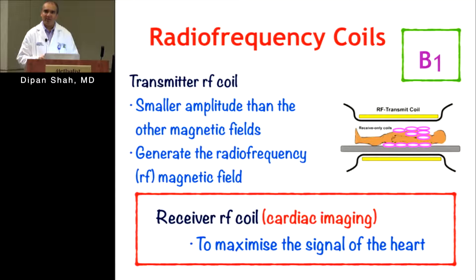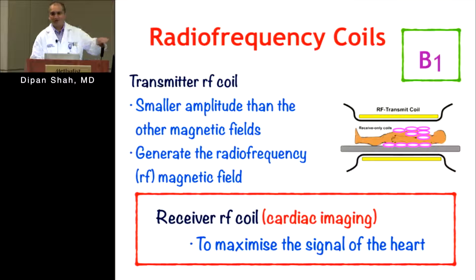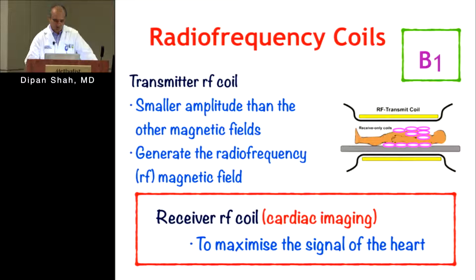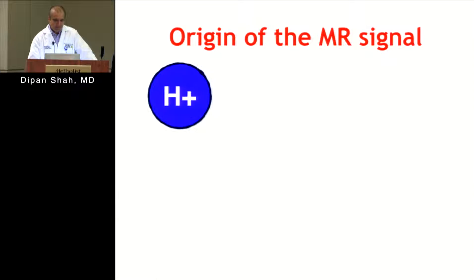It's like a radio station transmitting radio waves and a radio receiver receiving them. The closer you are to the radio station, the better the signal. As you drive further away, the signal gets weaker and you pick up more noise. So the closer your coils are to the patient, the better the imaging and the more signal you achieve relative to noise.